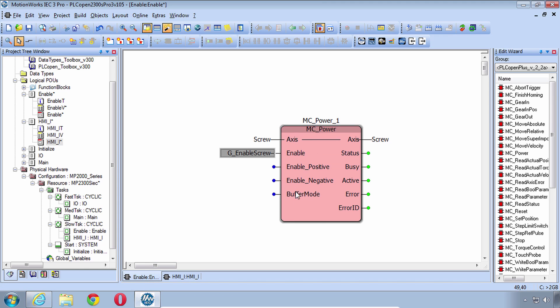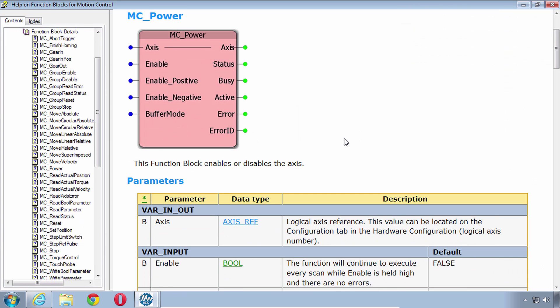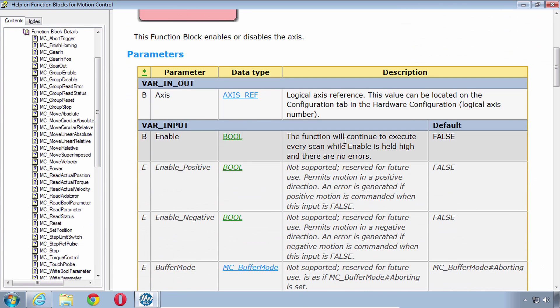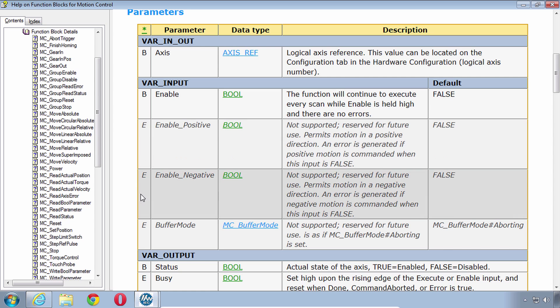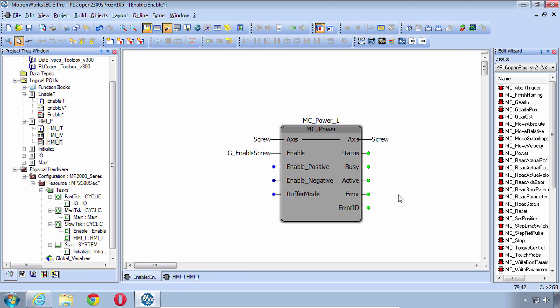Now what about these other inputs? Enable Positive, Negative, Buffer Mode. When you don't know what an input is you right-click and choose Help and we always have here a description of the input and output parameters. So you can see here that Enable Positive, Negative, Buffer Mode those are all Extended instructions and they're not supported. They're reserved for future use. So it's safe to leave those disconnected and this is really the most basic servo-on that we could possibly have.